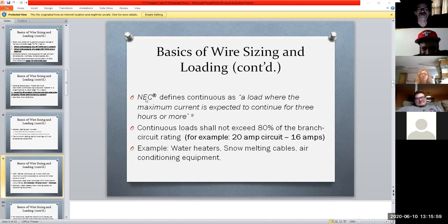So, and again, we always fall back to how does the NEC define it? They define continuous as a load where the maximum current is expected to continue for 3 hours or more. Now, that would be a factor we would have to consider, right? How often do you actually have something that's running in the house for 3 hours or more? Your typical receptacle, I mean, are you going to have a vacuum cleaner plugged into it running 3 hours? Your microwave, is that going to be going for 3 hours and that kind of thing? So the usual answer is no.